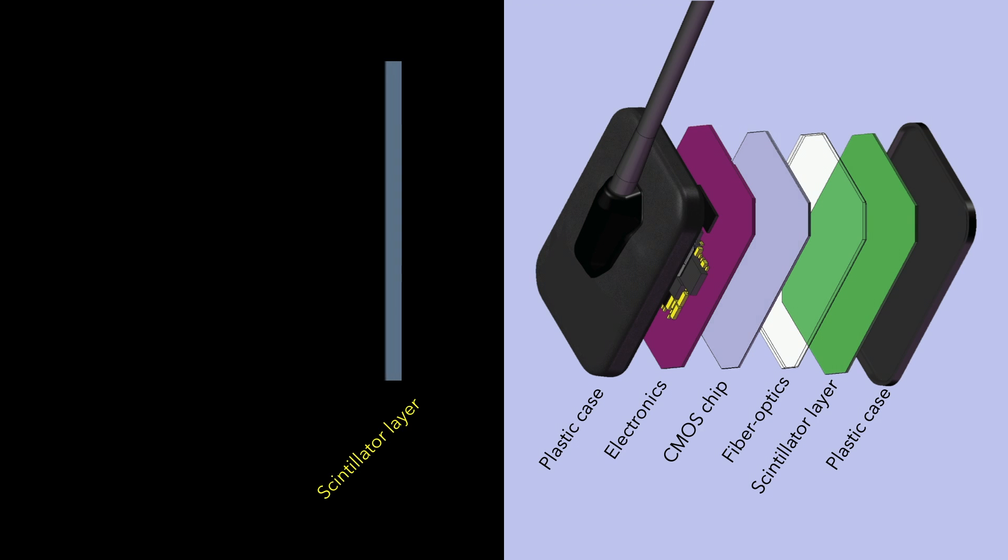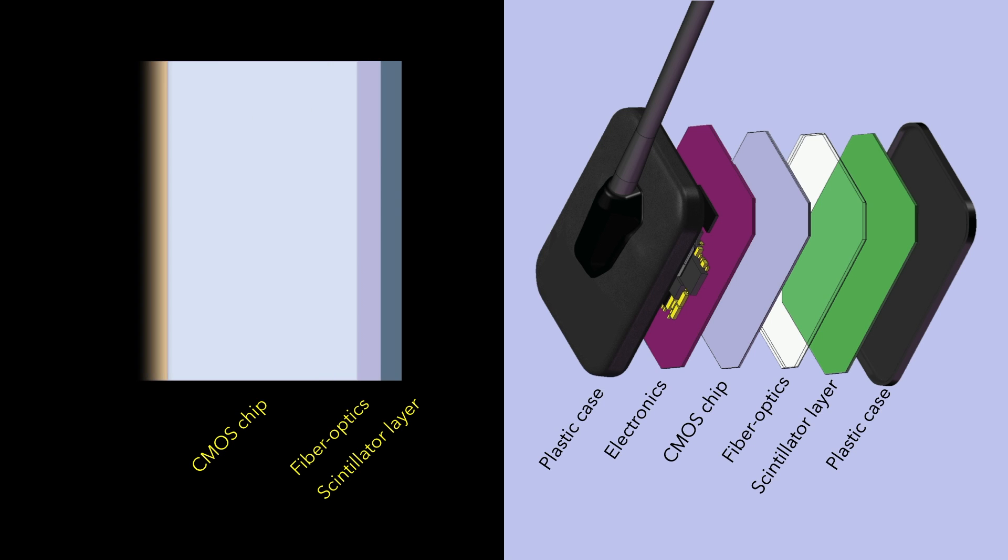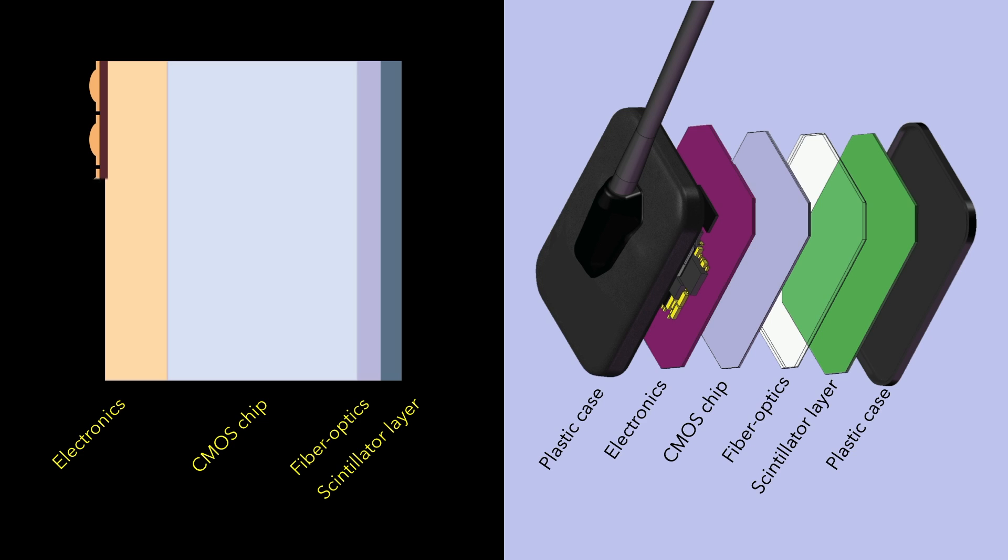Packed within this plastic casing is a scintillation layer, fiber optics, CMOS imaging chip, which really is the heart of this technology, and electronics that record the changes that happen in the chip and provide the data that go towards making the radiographic image.